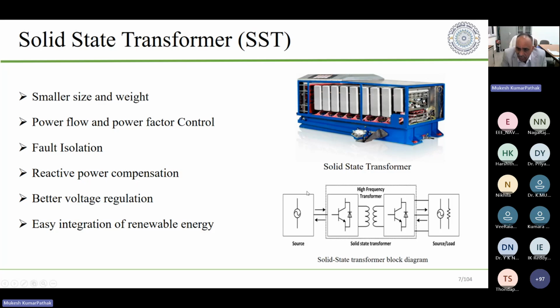The difference is that this would be higher voltage, typically 11 kV, 50 Hertz, and this could be 440 volt, 50 Hertz. So even though it looks like a transformation of voltage only, it is voltage transformation accompanied by frequency change also. There is an increase in frequency, then a decrease in frequency. So the solid state transformer will do both things. It will have two variables of control: one is the voltage, the other is the frequency.